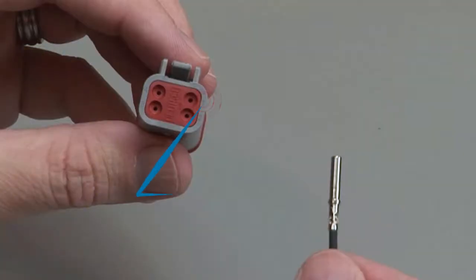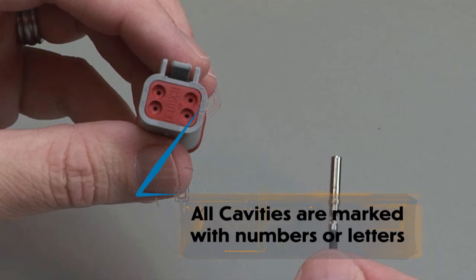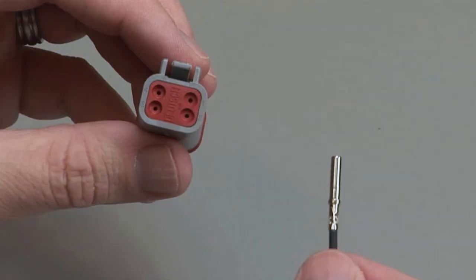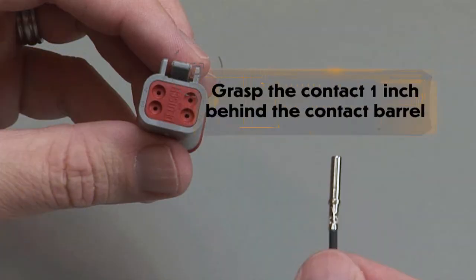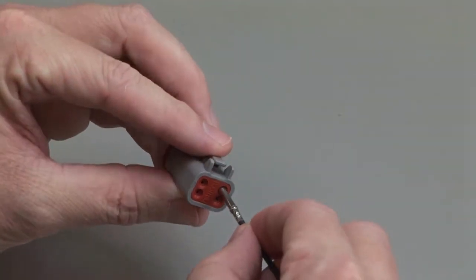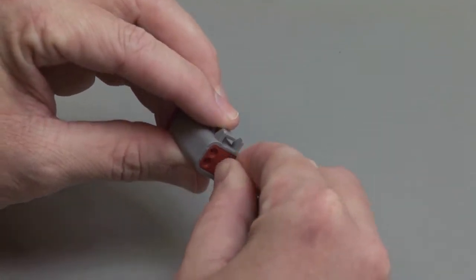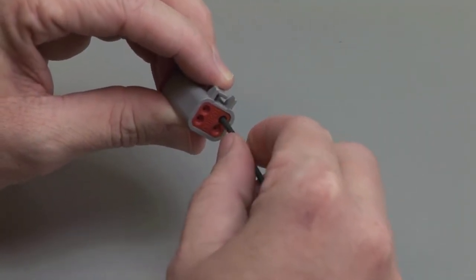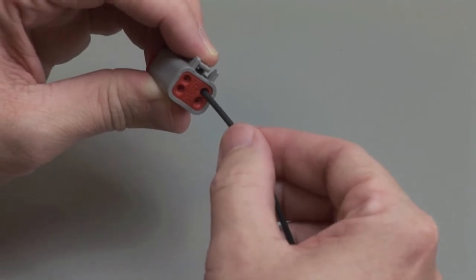All cavities are marked with numbers or letters. Grasp the crimped contact approximately 1 inch behind the contact barrel. Hold the connector with the rear grommet facing you. Push the contact straight into the rear grommet until you hear and feel a click. A slight tug will confirm that the contact is properly locked into place.